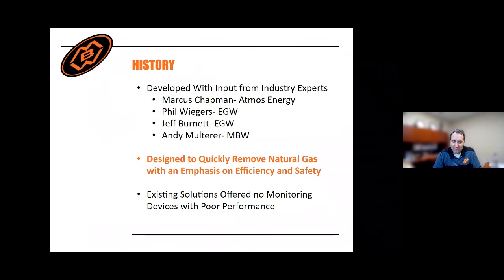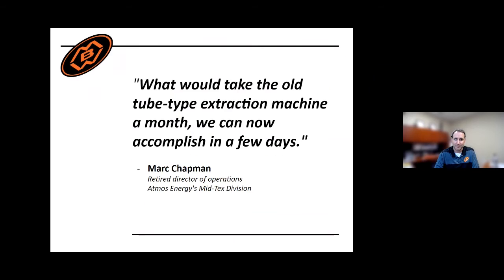This was just a little bit more on the history. Existing solutions really offered no monitoring along with poor performance. The VEU allows not only the productivity to get better, but it gives you a real live idea of what's coming out of the ground. So often as you're running the unit, if you're stuck at say 5% LEL for quite some time, that means you're still pulling a lot of gas out. And it's only when you get down to like 1% that it's really worth going and checking those bar holes to identify your pinpoint.